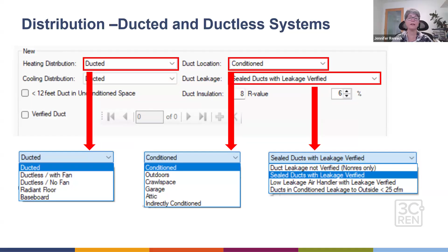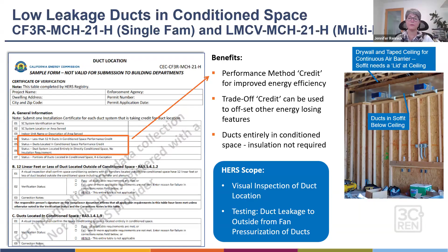But to give you an example, pick that low leakage ducts in conditioned space, for example, same options for multifamily projects. Now your HERS rater is going to come out and look for the visual inspection of the duct location, and then they're going to do duct leakage testing to show that the ducts are meeting the low leakage part. Plus, they want to see that the ducts are truly in the conditioned space. So in other words, those ducts need to be located, like in this example, below the ceiling plane, which will be taped, drywalled all around so that it's within the air barrier. And then those ducts are going to be within a soffit. That gives you an example of that. And then these are populated on the CF2R, CF3R forms, which is part of that whole permitting process.